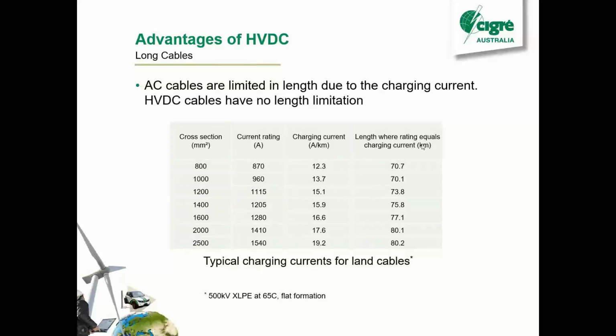This table is just showing some values that were pulled out for a 500 kV XLPE cable. You can see that for this particular cable, once you get up to 70 or 80 Ks in length, you're completely consuming the cable's rating just in charging current. So you've got no ability to send any more power on that cable at those lengths. And this is a land cable; for submarine cables, it's even worse. They tend to have even higher capacitance. So that's pretty much the main reason HVDC was adopted in New Zealand, because of that submarine cable crossing.